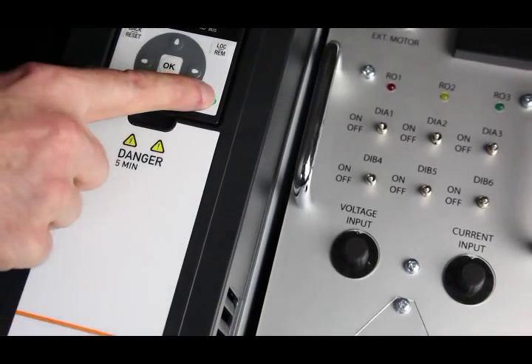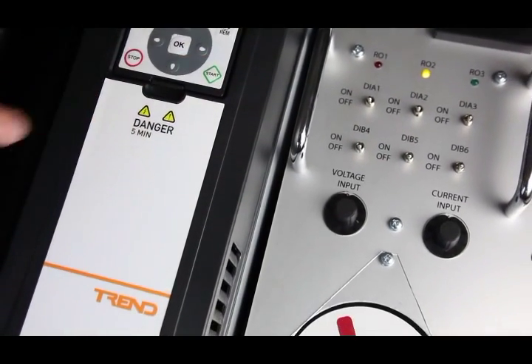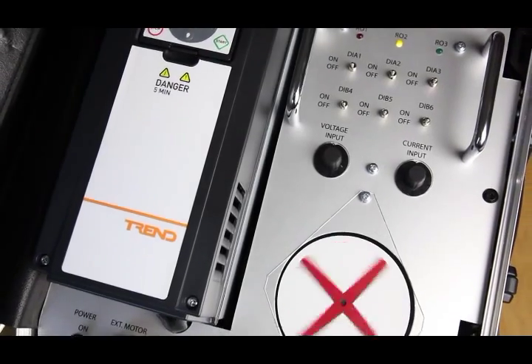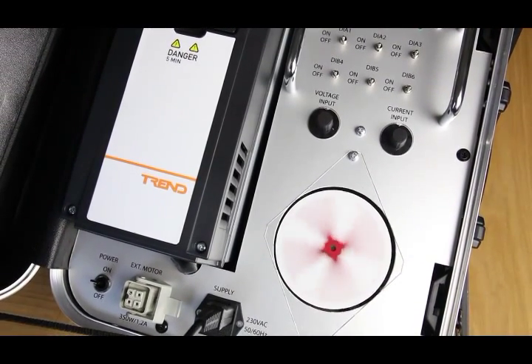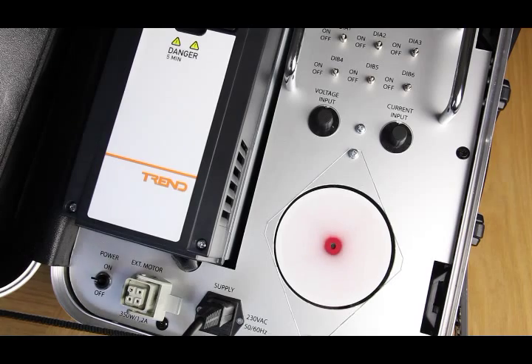We can see that the motor starts slowly as the wizard was set up for a pump application. If we had chosen the fan option instead of the pump option, the startup would have been quicker.